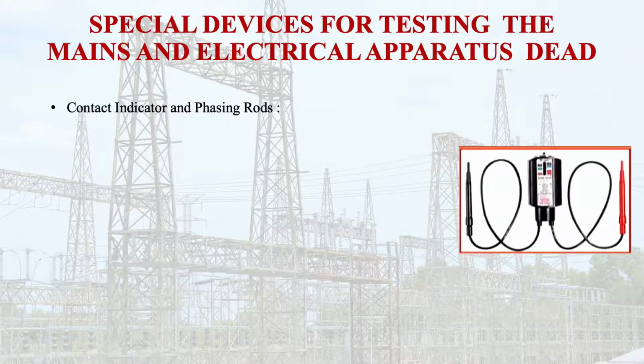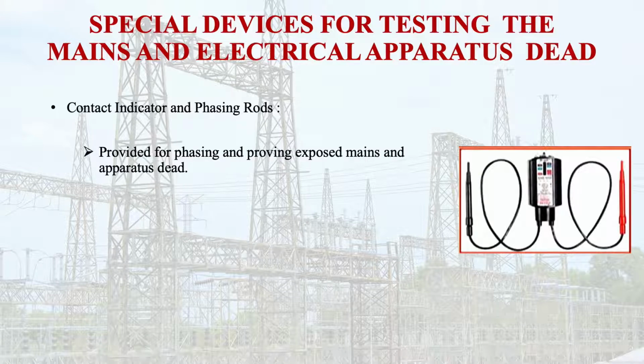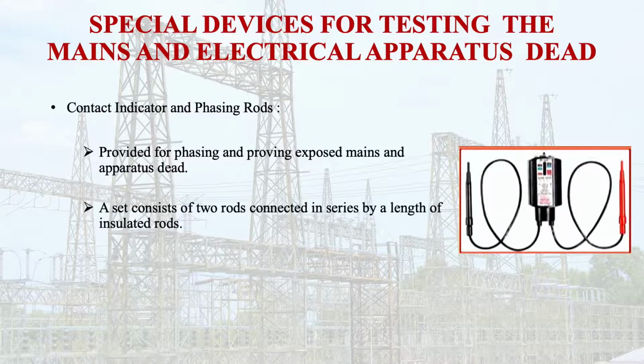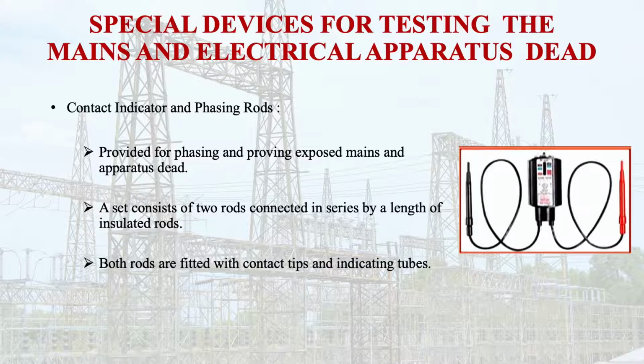Then the contact indicator and phasing rod. This is also one of the special devices for testing that the mains and the electrical apparatus are dead. The contact indicator and phasing rods are provided for phasing and proving exposed mains and apparatus dead. A set consists of two rods connected in series by a length of insulated rod. Both rods are fitted with contact tips and indicating tubes.